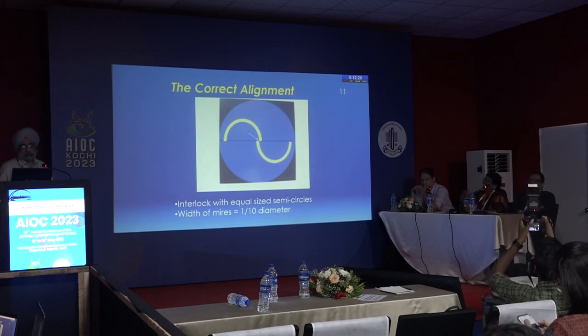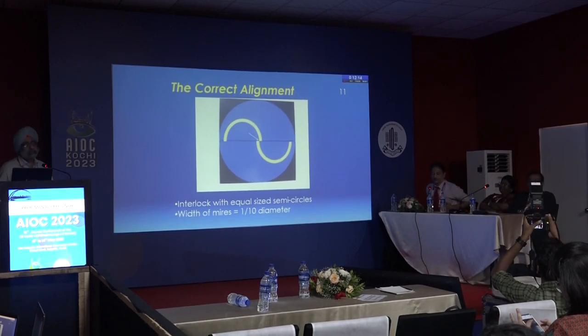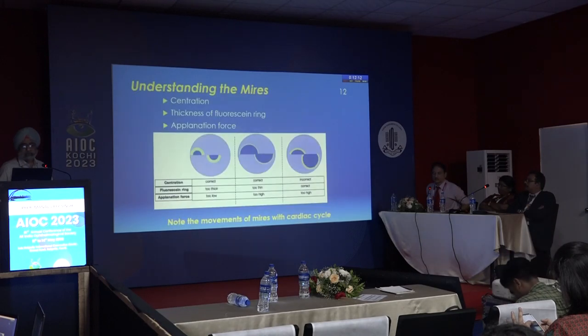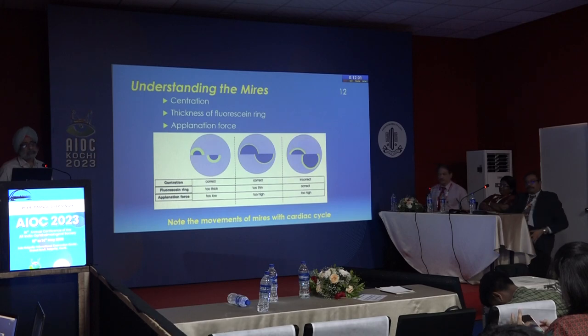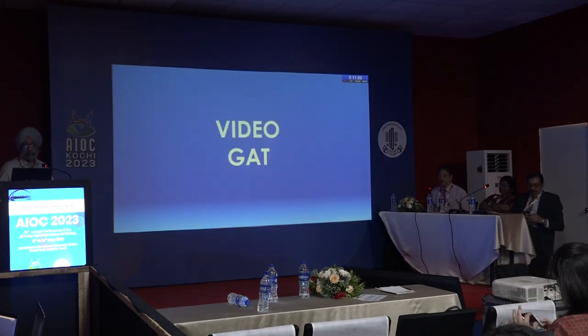For correct alignment, the two semicircles should interlock with equal size, and the width of the mires should be around one tenth of the diameter. Problems can arise from centration, thickness of the fluorescein ring, applanation force — if the rings are thick, you need to wipe the patient's eye; if they are thin, you need to add more fluorescein.